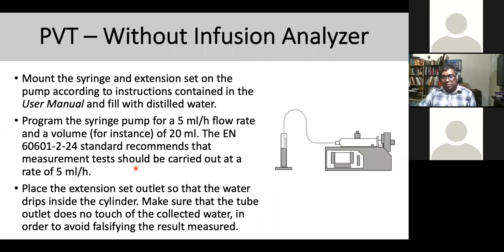So when you run the syringe pump, this particular line is going to send the fluid to the cylinder line, and you're going to compare the reading basically. So if you see you delivered the 20 to the system accordingly, that means it's good. And you can see the checklist, what's the tolerance. Normally it should be somewhere 5. So that's how it works actually.